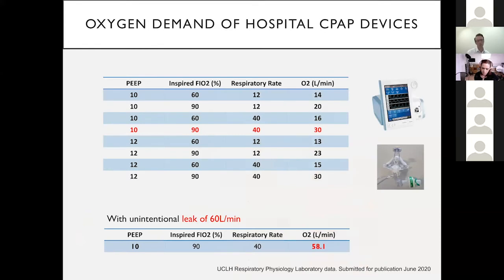So bringing through some data that we generated in our hospital to try and understand this. Whilst the manufacturers will likely refer to an average oxygen use of 15 liters a minute with the bespoke hospital dedicated devices, that oxygen demand does vary according to the PEEP provided, the respiratory rate, and the required FiO2.